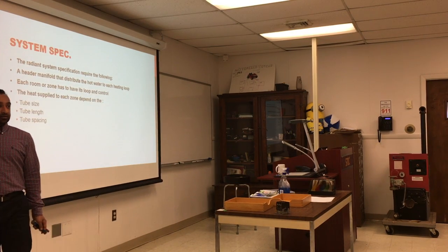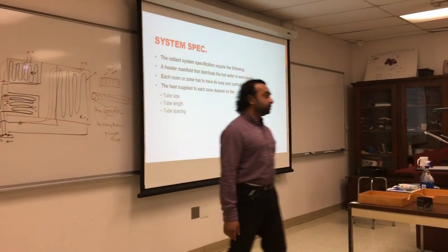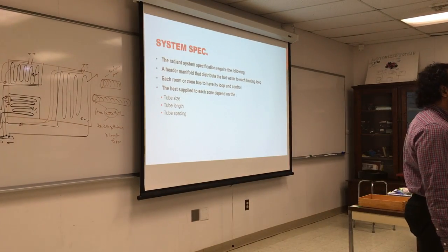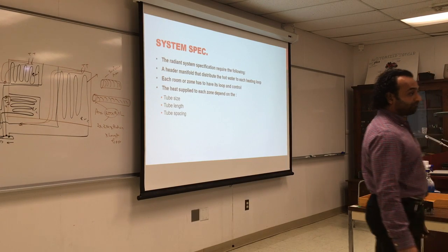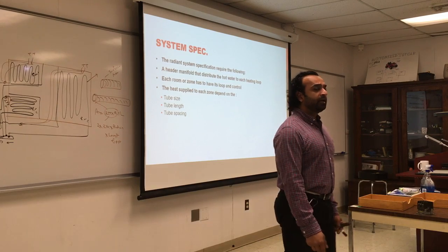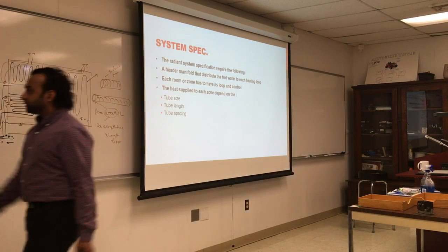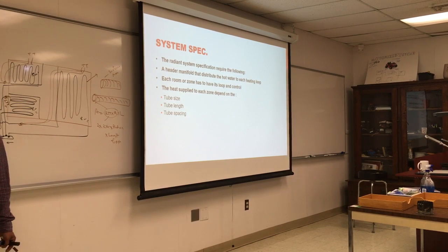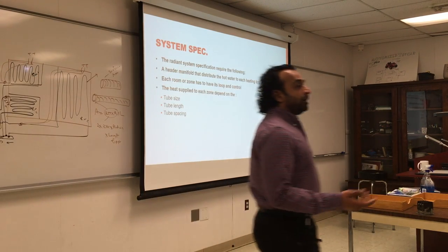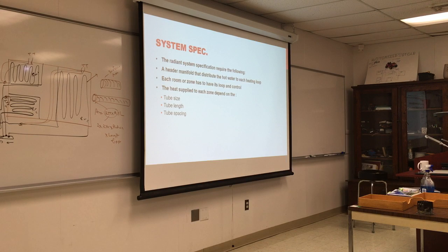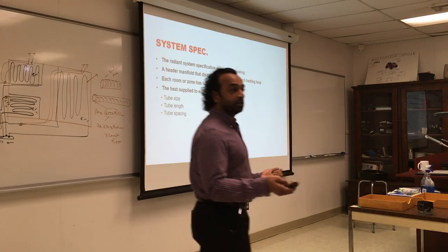I've seen people put PEX, but PEX is fairly new. I would not put PEX in a place where I cannot get access to it, in case it leaks or sags, or under a floating floor. Sometimes the system might have a fault, and you might exceed the heat limitation for copper, for PEX, and that will ruin them. Again, it's a control issue, but you don't want that kind of fluid pipe inside the room, because that is going to lead to a big leak, and we said leaks are very problematic.